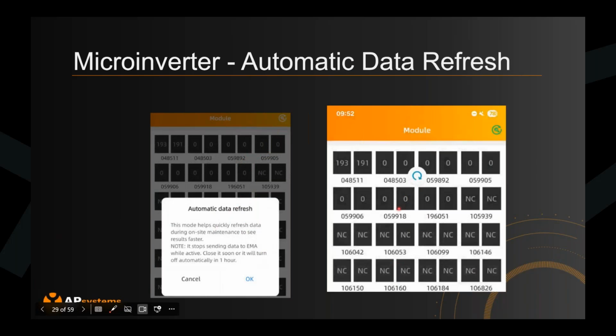Note that according to NEC, the microinverters will only produce power after they see AC voltage for 5 minutes, so this feature does not override that. It only overrides the polling. So you might still find that when you turn on AC, you won't see power coming through the microinverters until 5 minutes afterward, because of NEC code. This feature only increases the polling frequency of the microinverter data.